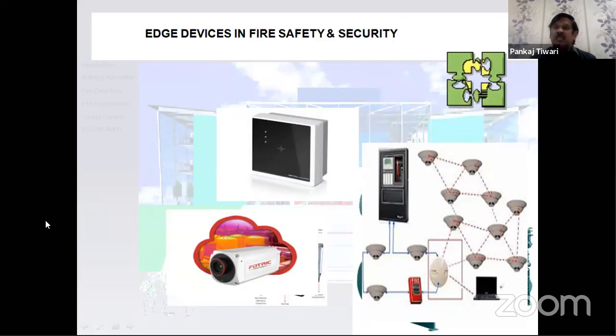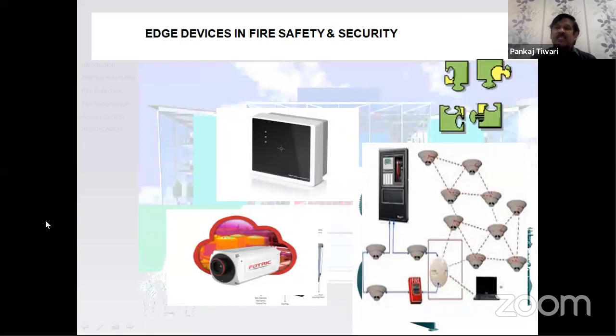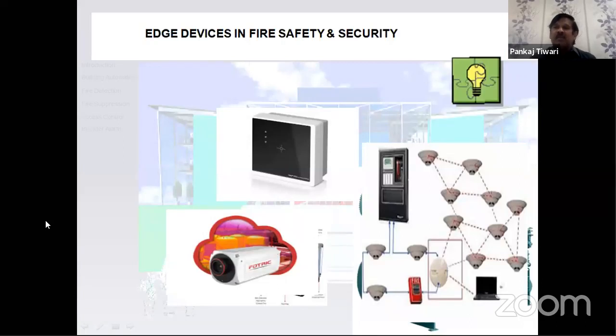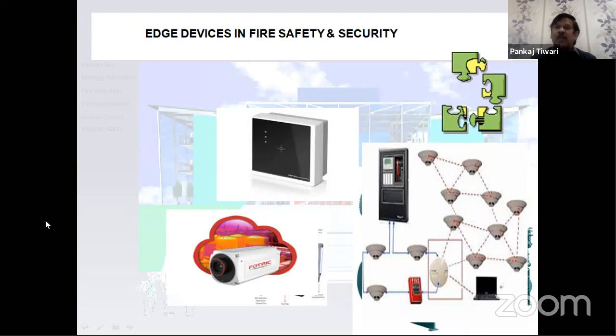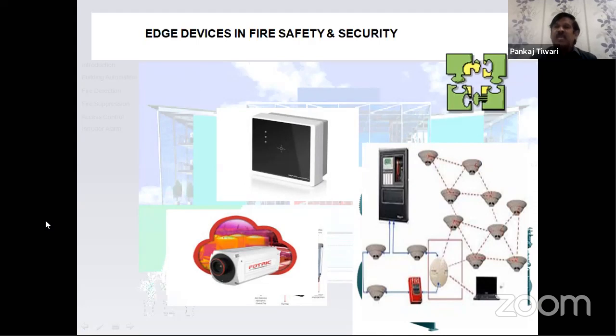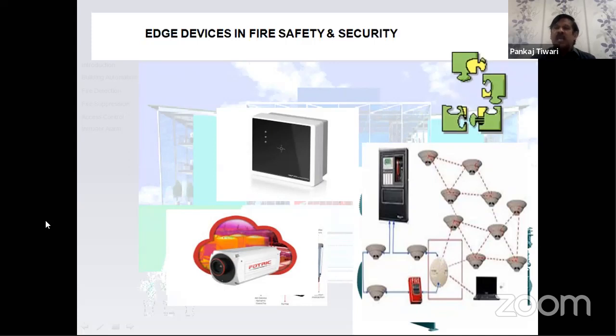But the only thing missing right now is that it's important for all manufacturers in the country to know that their wireless system with the fire alarm panel should conform to all NFPA requirements. The units cannot work in silos. As NFPA says, if fire takes place on one particular floor, the equipment of that floor - like air handling units, fire damper operation - should take place automatically from the wireless fire alarm panel. So even the devices need to be connected wirelessly or remotely to this fire alarm system.